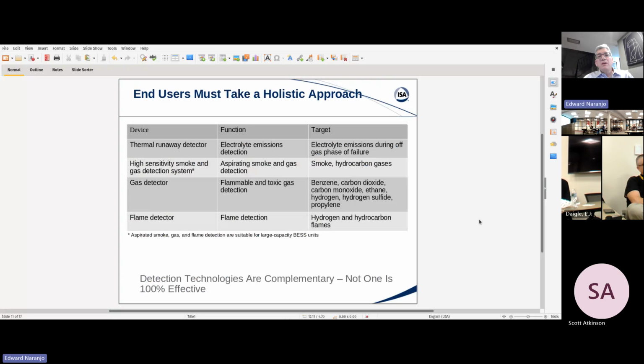Now, what I would suggest if we were to use active fire protection is to have a holistic approach to it. It is often the case, and I have found this, that operators use one single detection method, and most likely they believe that that is enough. I would not be surprised that APS, for example, back in the example that I used in the safety moment, thought that having a single extinguishant with some sort of heat sensor was enough. But as you can see, there are methods or developing accidents that can foil that detection method. So the best protection is defense in depth, just like with cybersecurity. Just don't rely on a single barrier.